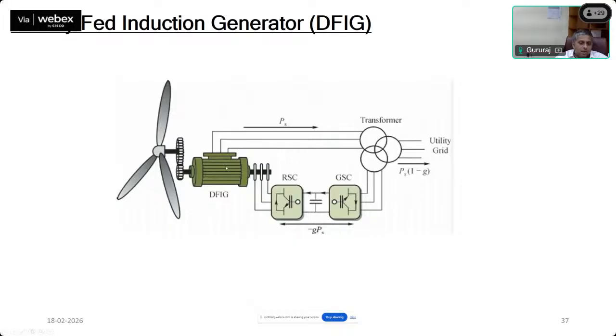Now suppose there's excess wind velocity, so the synchronous speed is crossed and you're generating at, say, 51 or 52 hertz. This isn't ideal since the grid needs 50 hertz. So the rotor side converter recognizes this additional component of power that's in excess, pulls it out, and pushes it to the DC link capacitor.